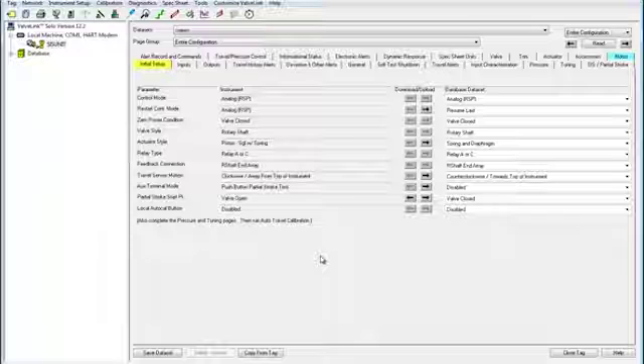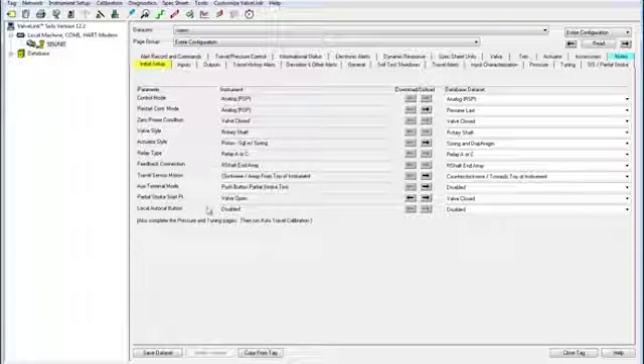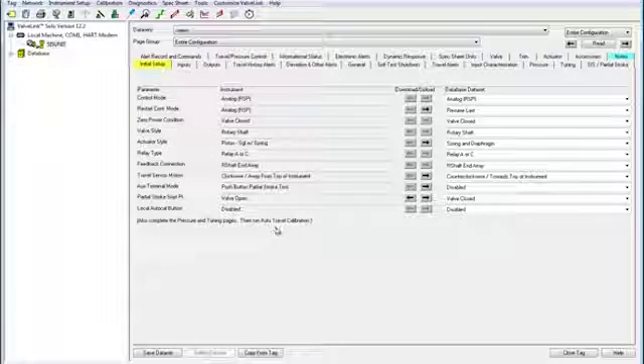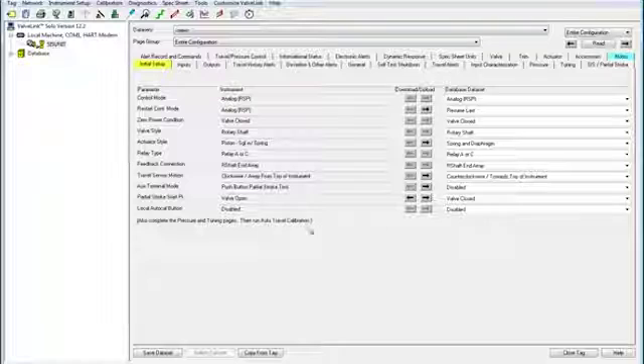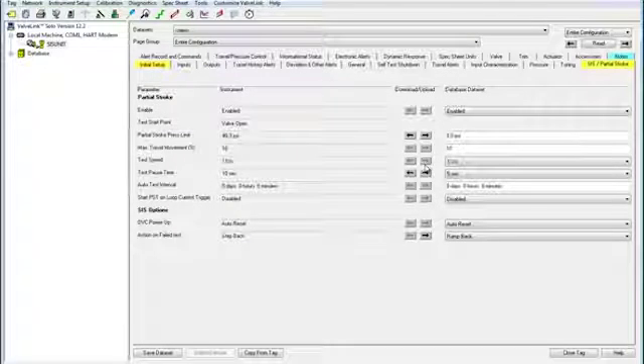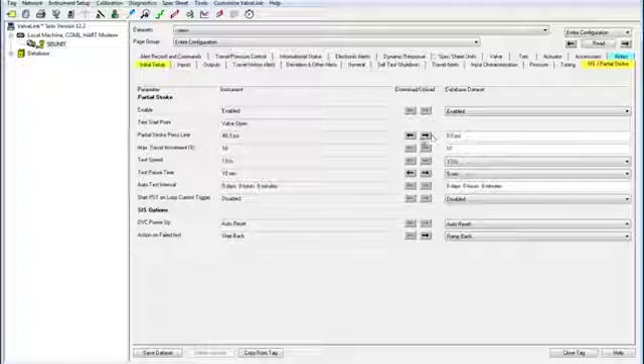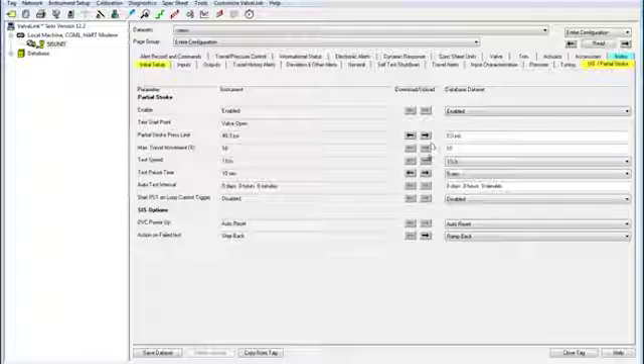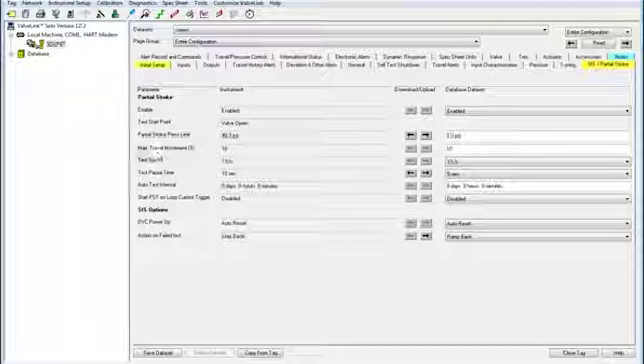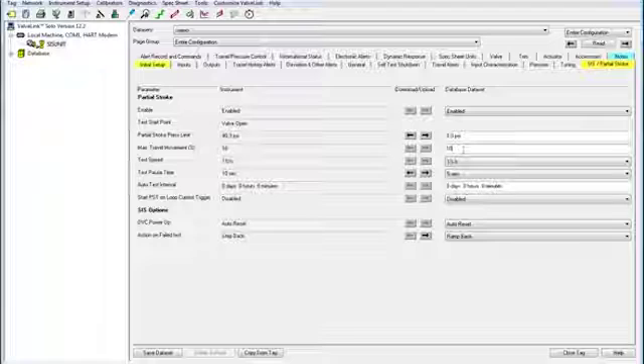You can edit a lot of options here, but we are going to focus on the SIS slash partial stroke tab. Click it, and here you can see your partial stroke test options. You can adjust these as needed. I'm going to change the maximum travel movement from 10 to 15.